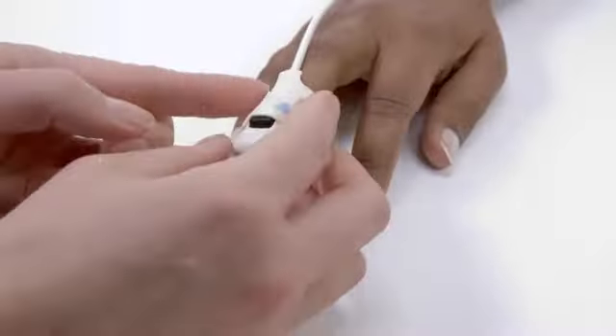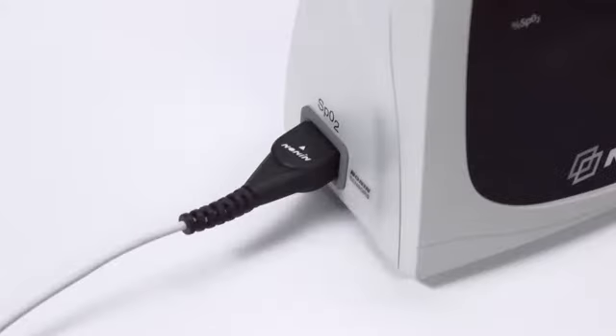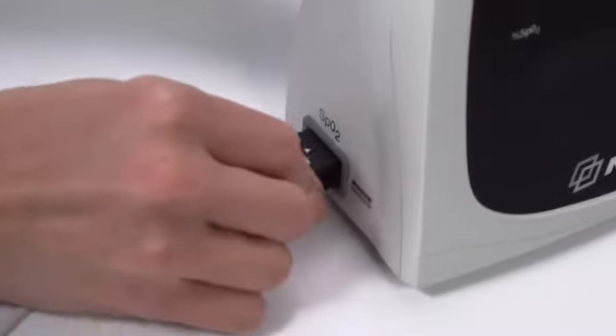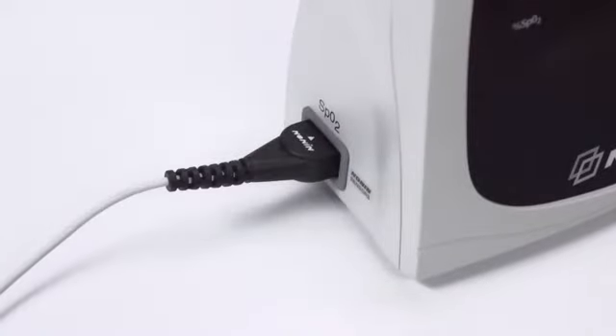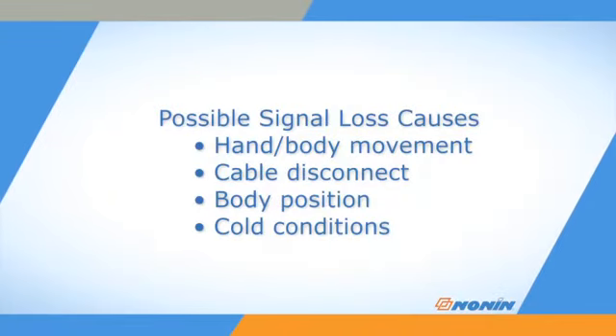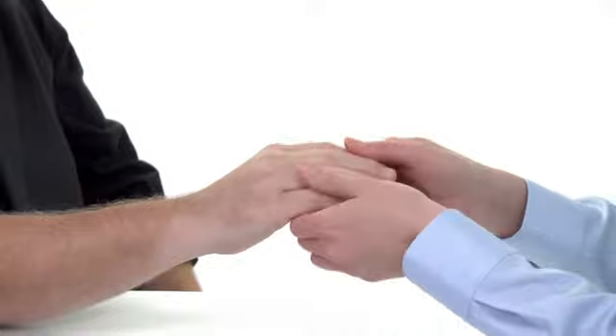It's a good idea to check pulse signal quality at startup and adjust the sensor for a stronger reading if necessary. Signal loss from the sensor is possible with hand or body movement or disconnection of the cable. Check and correct the position of the sensor if it has moved and recheck the sensor connection to the oximeter. Signal can also be reduced by body position or cold conditions, which may reduce blood flow. Relax and warm the hand to restore stronger blood flow.